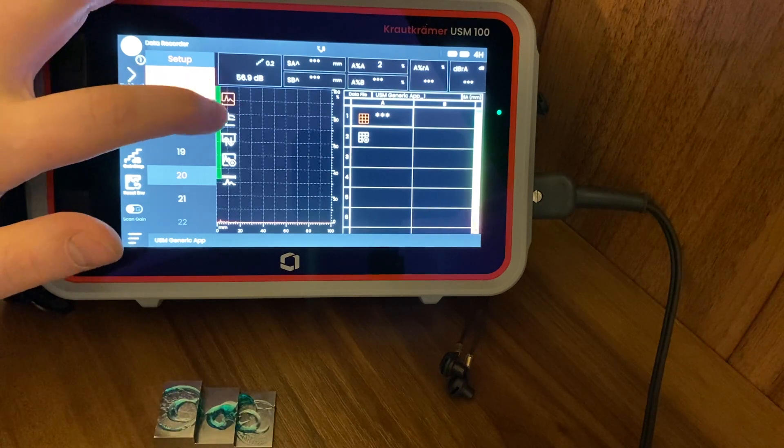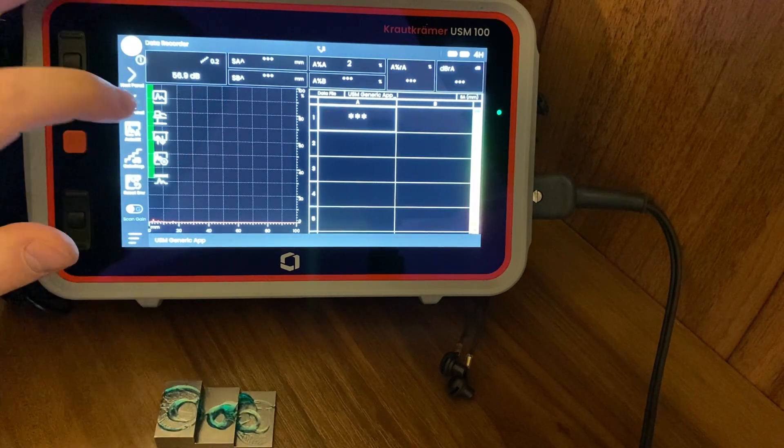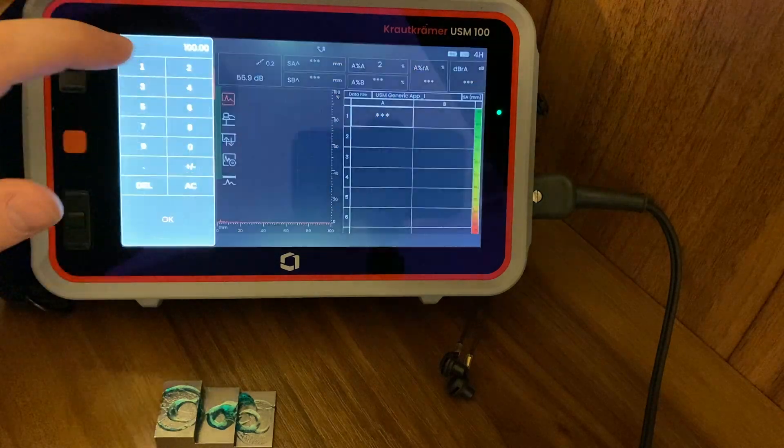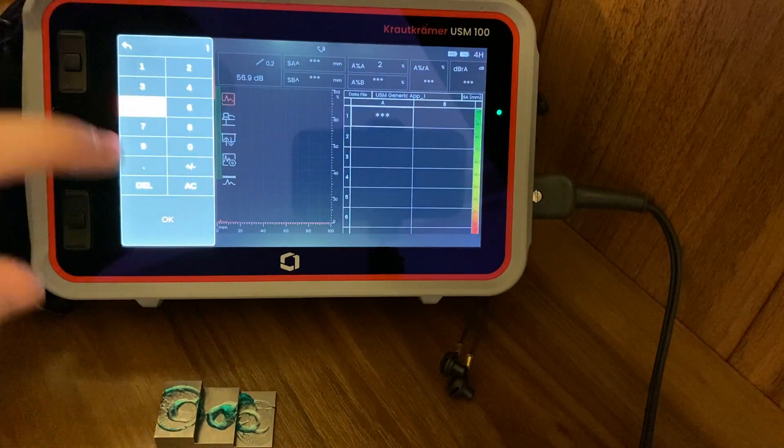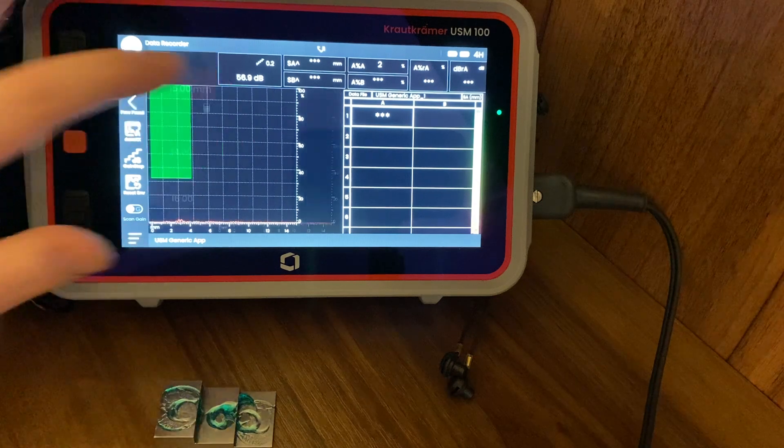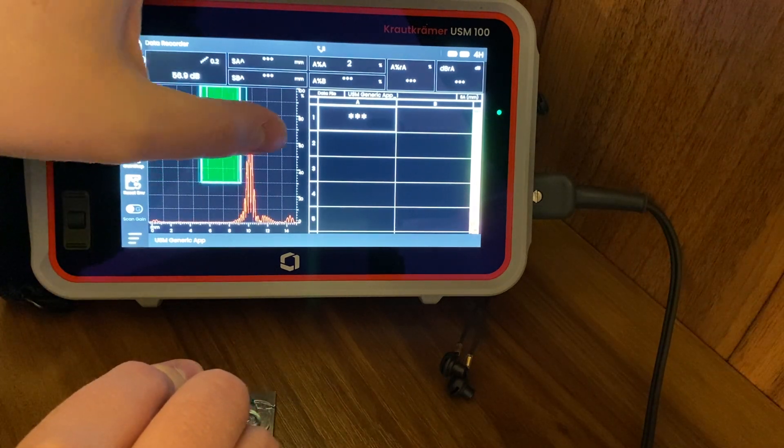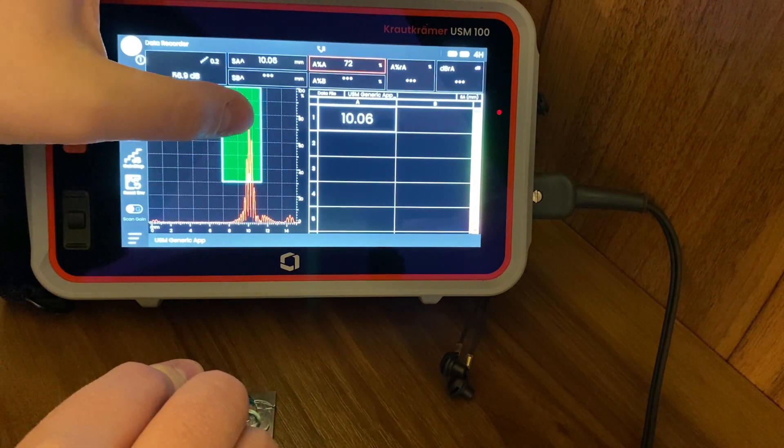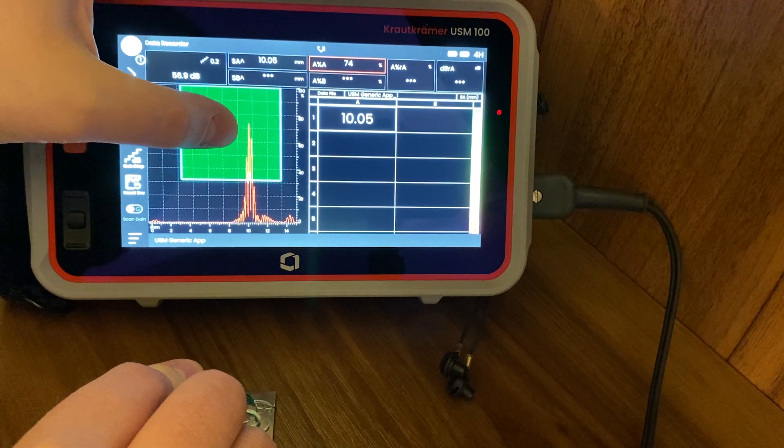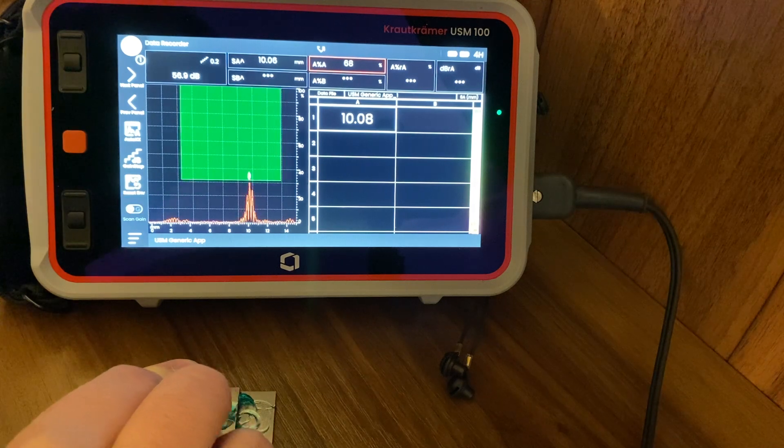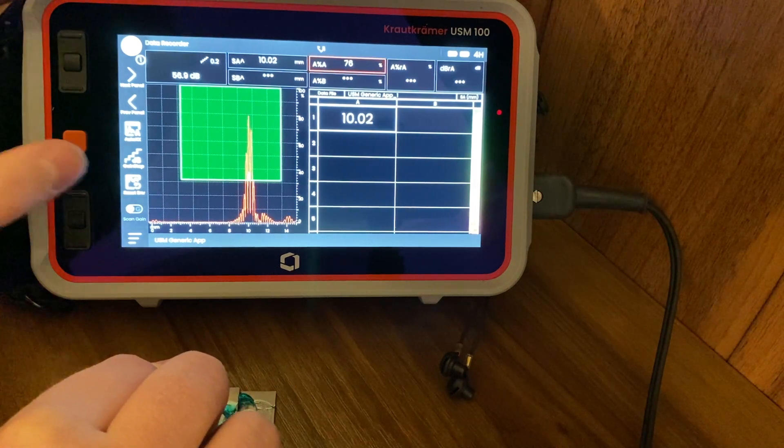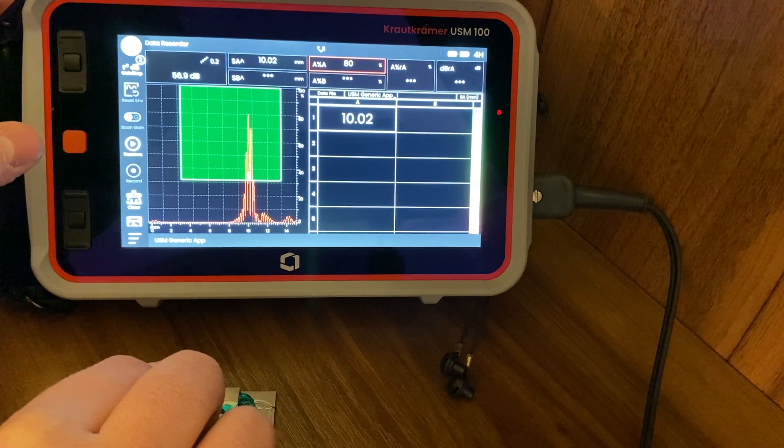So you would start then - you would reduce your display range. Let's say the part is 10 mil, so let's put up 15 here. And you then move your gate. You can widen that gate if you want just by dragging on one side. A lot of people ask about this gate - it's a box. They're used to a line; this is the same thing, it's just colored in for easy seeing. Then you can go down here and hit the record button.